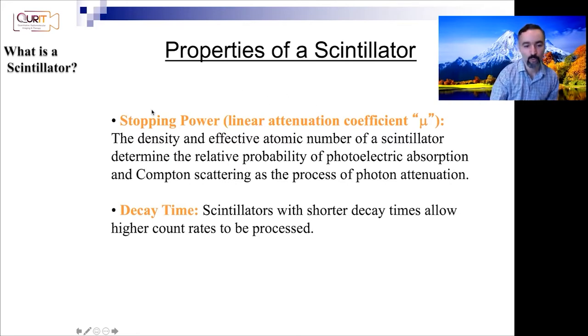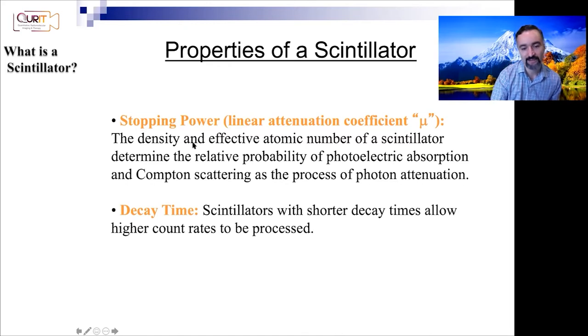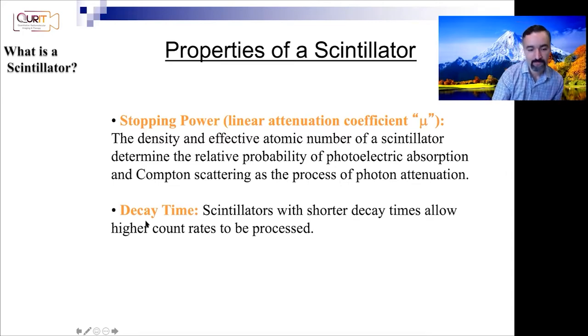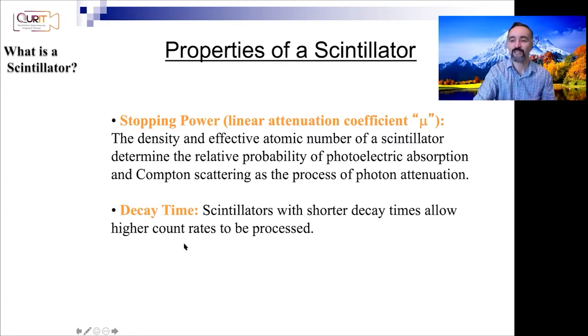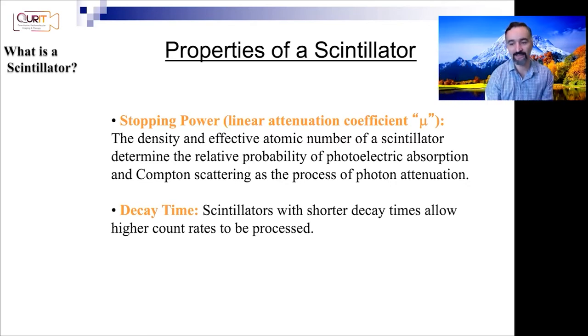There are a number of important properties of a scintillator. Stopping power: you have to find a way to stop that highly energetic photon — 140 keV for SPECT or 511 keV for PET. The material has to be dense, so the density and effective atomic number really determine its ability to attenuate photons through photoelectric absorption and Compton scattering. Decay time is also very important. A shorter decay time allows higher count rates to be processed, because if it takes too long for the excitation-return cycle to complete, the next event won't be processed properly — resulting in high dead time.